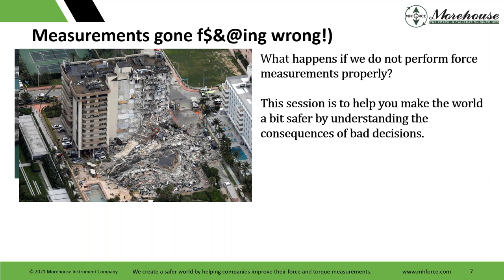UKAS LAB 48 is a really, really good document if anybody wants a good read, which basically puts the decision back onto the customer — and I think that's the intent of ISO IEC 17025 as well, which means the customer should be telling you what they need. That document aligns very well with JCGM 106, which is another free document. All recommended reading if you're into decision rules and want to learn more. And then there are paid versions like ASME and some other ones.